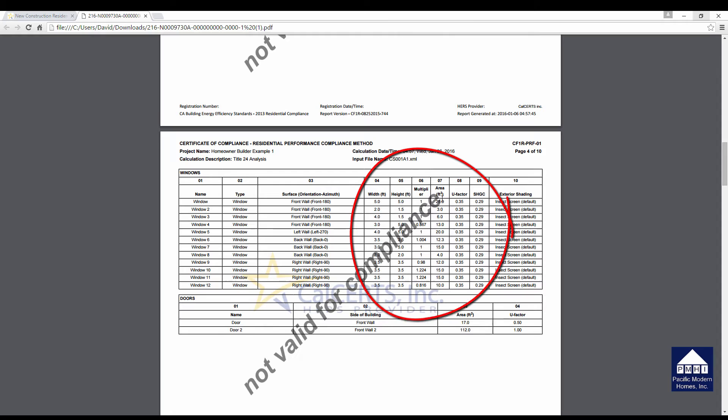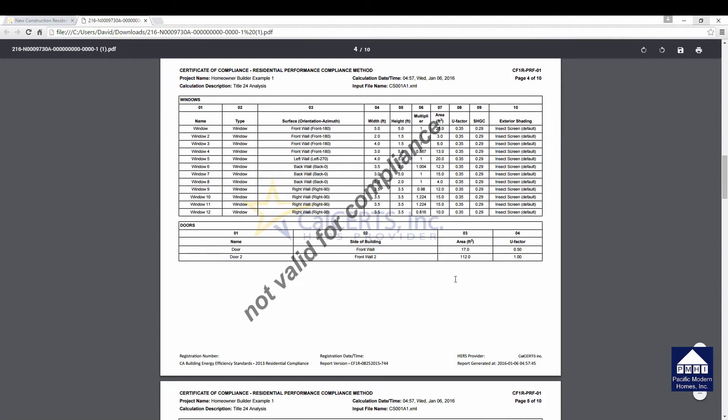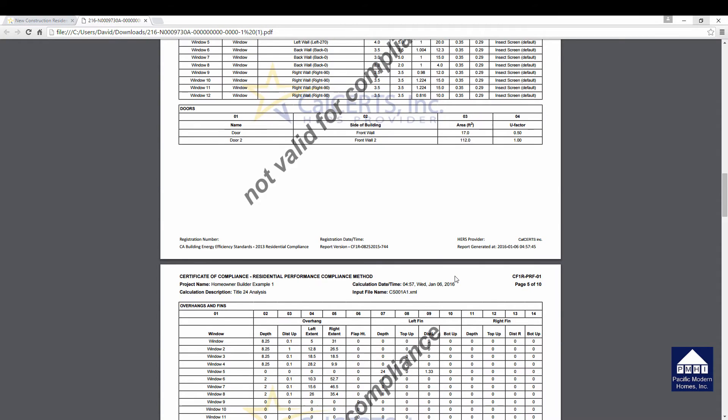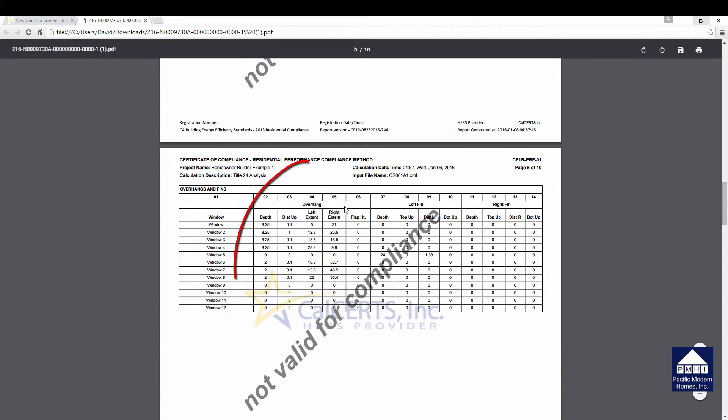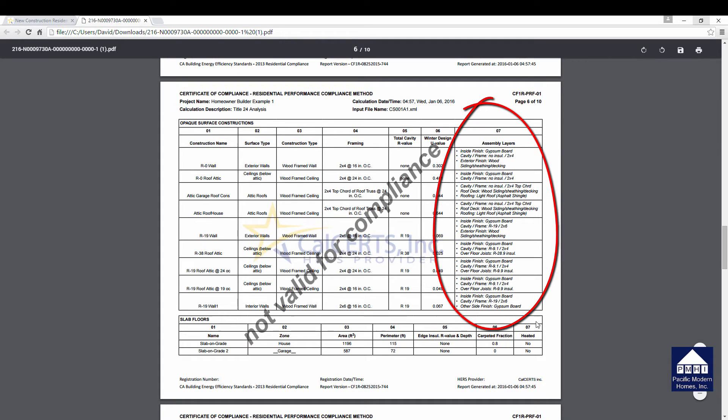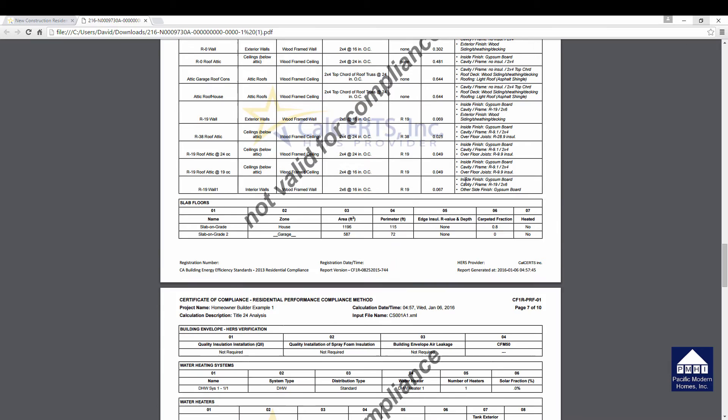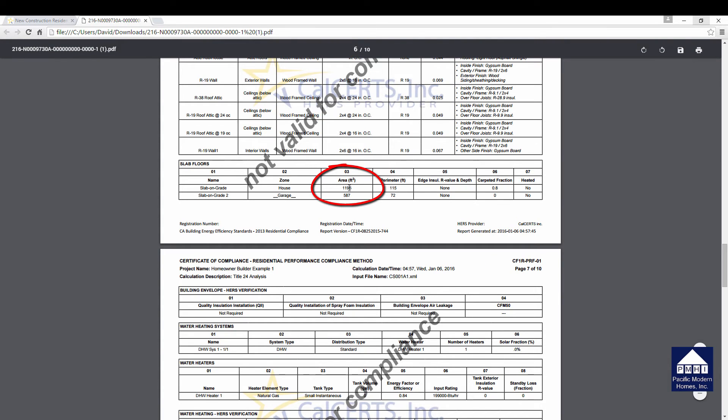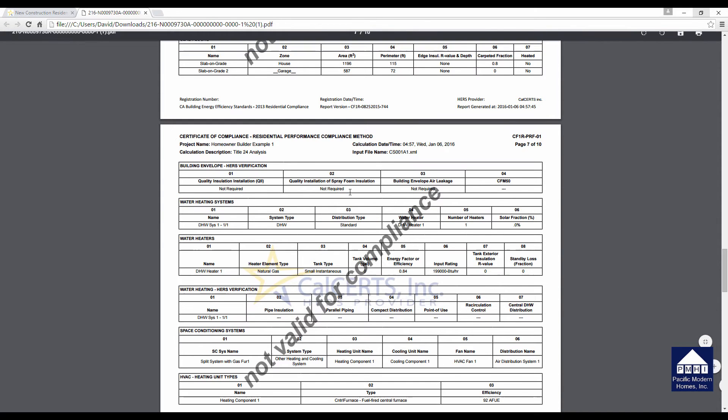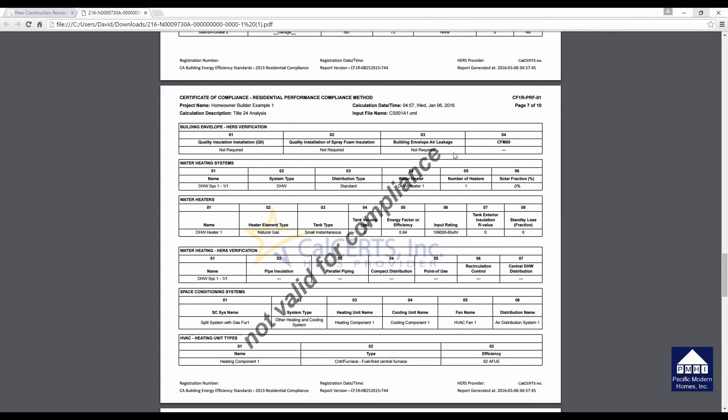It will tell you the number of bedrooms that the house has, the square footage, the average ceiling height. It will give you the assumptions for the roof, wall, and ceiling insulation. If you had a floor, it would be listed right here. This gives you all the information on the windows. It gives you the window sizes, the area, the U-factor, the SHGC. All of the critical information on the windows associated with the project. If you have overhangs for the windows, those are all listed here. All of the assumptions on all the different walls, roofs, ceilings, floors, all of that information is provided here.